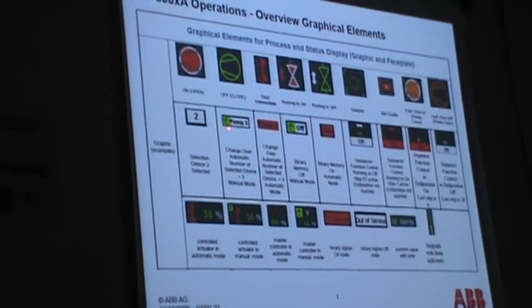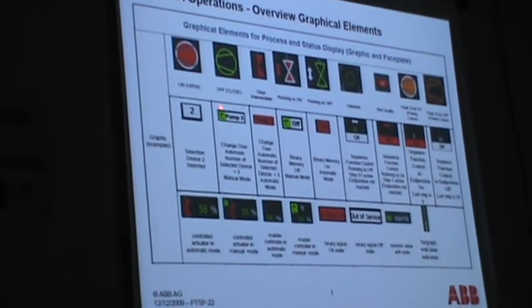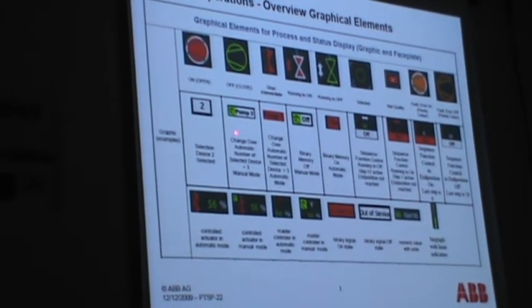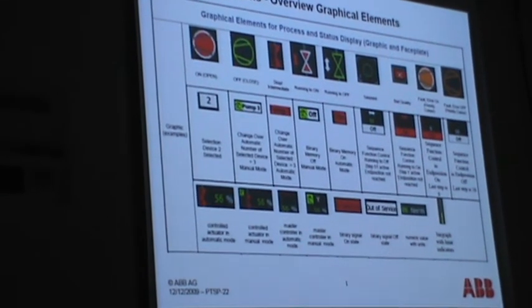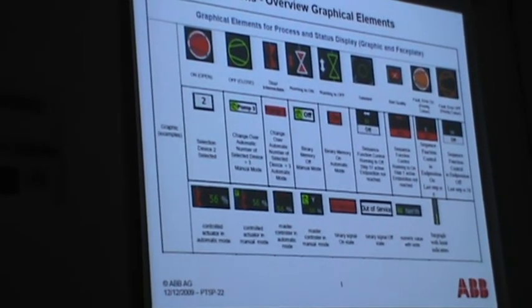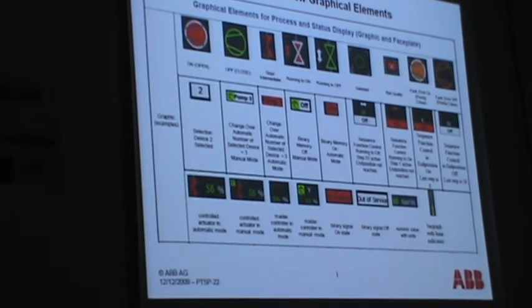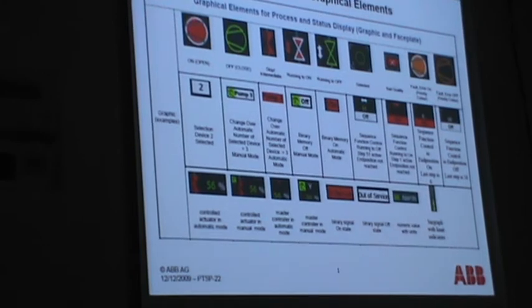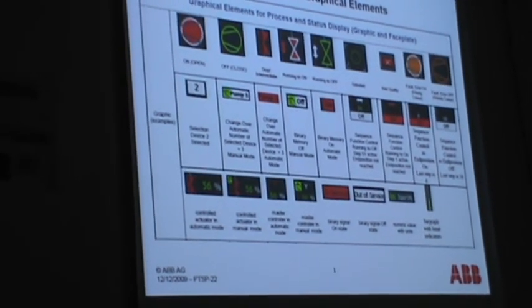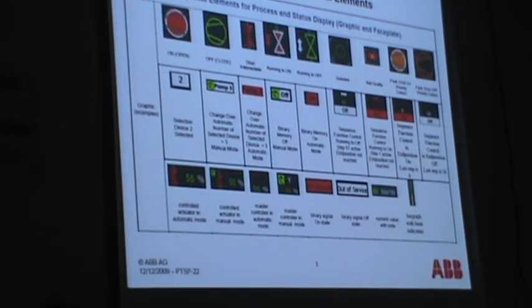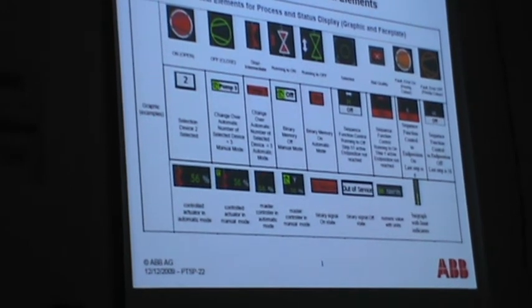So this is in manual. There we have 2 different modes, manual mode and auto mode. In manual mode, there will not be any changes. Manual mode will not work with your flow. Only the auto mode will work with your flow. So you need to keep the changeover in auto mode if you want auto. Yeah. So the pump will start automatically if there is any flow requirement.